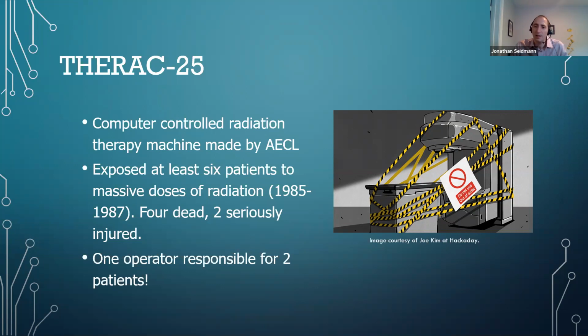So the physicist then found another cancer center that had a similar machine, actually not the Therac 25, but one of the earlier units, and called them in Chicago and asked them to follow this procedure for making the unit fail, because they were able to repeatedly make the unit fail. So they called the other unit in Chicago and said, hey, follow these instructions. But when the unit in Chicago followed the instructions, the machine would not follow the same path and it wouldn't deliver the same units of radiation. Essentially, this tripped a hardware interlock, a hardware failsafe on the machine, and would cause the system to blow a fuse, preventing the machine from delivering any dose at all to the patient. This was kind of curious to the physicist at the cancer center in Tyler, because he said, what? We don't have this hardware fail-safe in our system. So what happened?